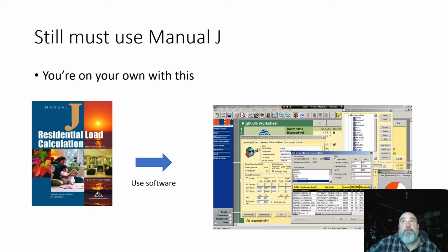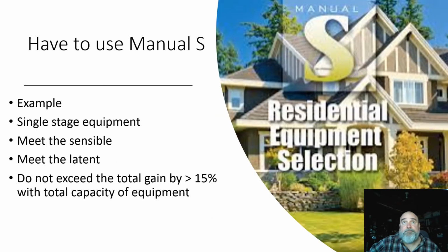Still got to start off with doing a load calculation via Manual J. There's no free lunch or bad rules of thumb that we're going to use to determine what size equipment we need. There's the book over there on my left. Computer programs are definitely the way to do things. Got to use Manual S. Manual S is as, if not more important than doing a load calculation. There's a lot of people selecting equipment using, again, bad methodologies instead of finding the proper way to select equipment.